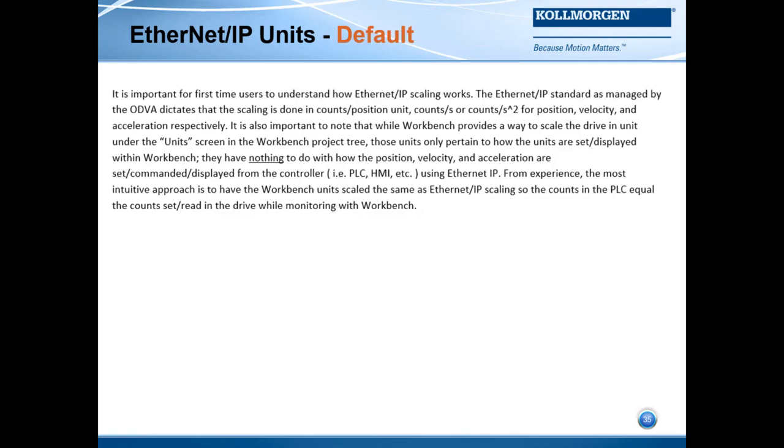From experience, the most intuitive approach is to have the Workbench units scaled the same as the Ethernet IP scaling, so the counts in the PLC equal the counts set or read in the drive while monitoring within Workbench.